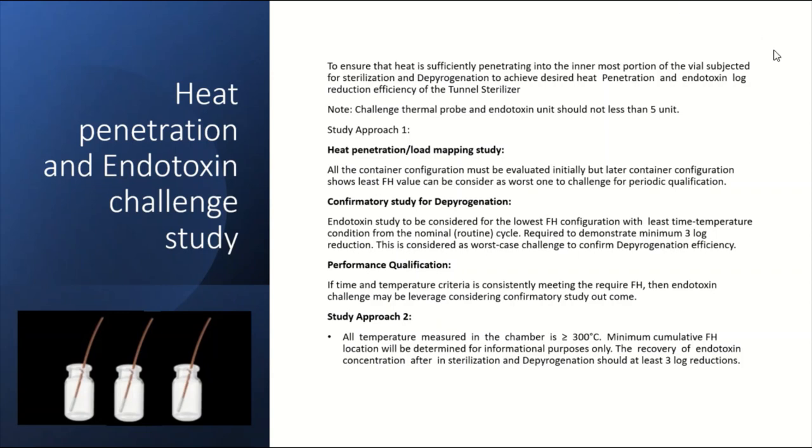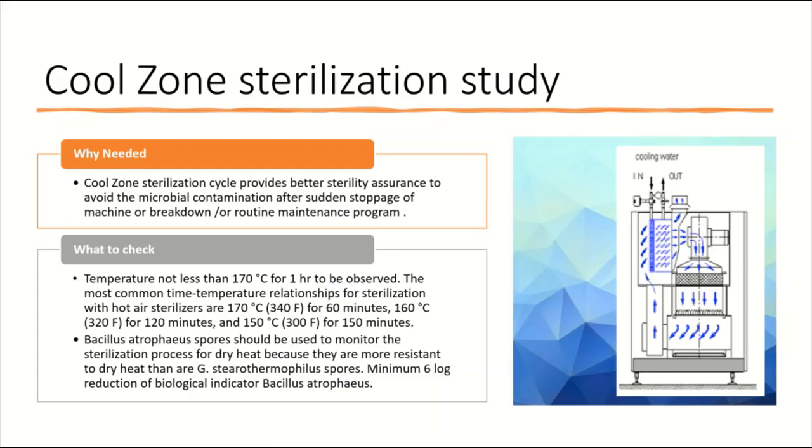To summarize once again, approach one is talking about mapping all the containers, getting the containers with the least Fh value, performing depyrogenation challenge with that worst-case configuration, and then qualifying your configurations. If you achieve low Fh, then endotoxin challenge is not required. Approach two is pretty simple where we can do more than 300 degree temperature. The USP expectation is the set of temperature and time which will achieve your three log reduction is sufficient. There is lots of misconception—people talk about two or three minutes at a certain temperature as a requirement, but no, there is no time and temperature requirement. It is up to you to decide how much temperature and how much time is required to get at least three log or more than three log. At least three log is required to claim depyrogenation.